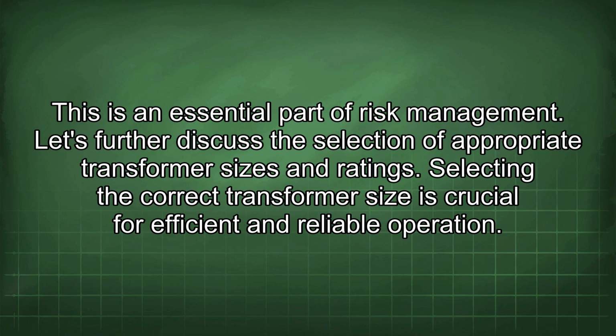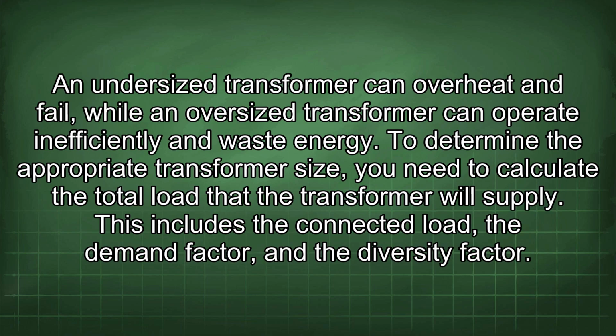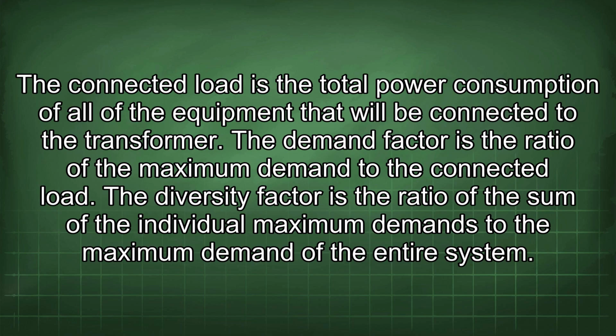Let's further discuss the selection of appropriate transformer sizes and ratings. Selecting the correct transformer size is crucial for efficient and reliable operation. An undersized transformer can overheat and fail, while an oversized transformer can operate inefficiently and waste energy. To determine the appropriate transformer size, you need to calculate the total load that the transformer will supply. This includes the connected load, the demand factor, and the diversity factor. The connected load is the total power consumption of all of the equipment that will be connected to the transformer. The demand factor is the ratio of the maximum demand to the connected load.